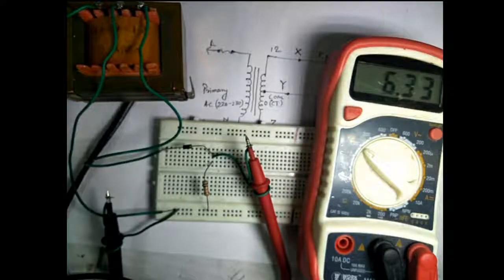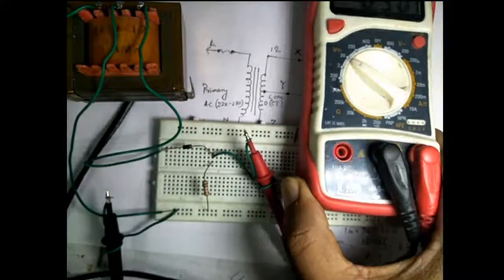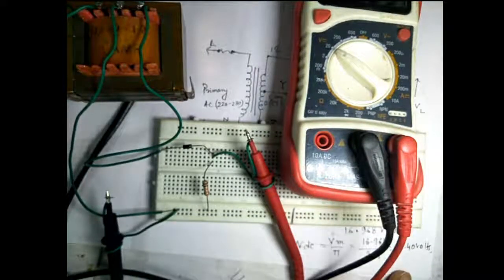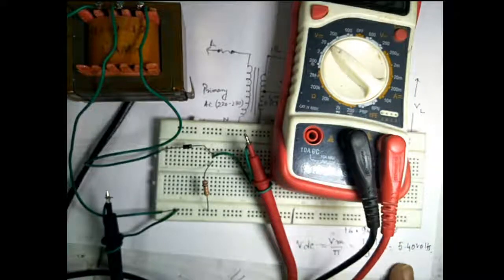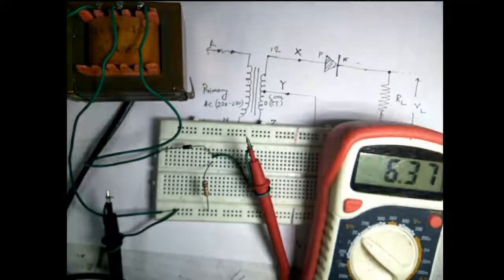Now if we switch on the transformer, what we can see is the voltage reading is around 6.36, but we were expecting a voltage of 5.40. The voltage that we are getting here is 6.38. This may happen if the voltage at the secondary side is greater than what it is written.